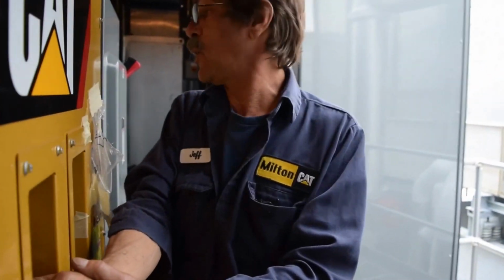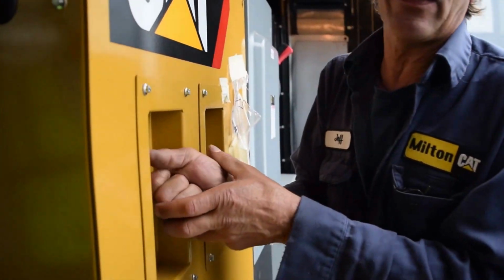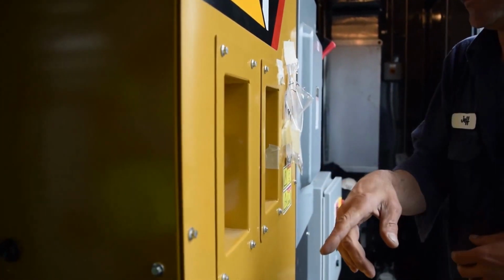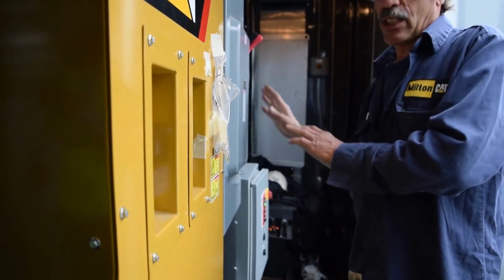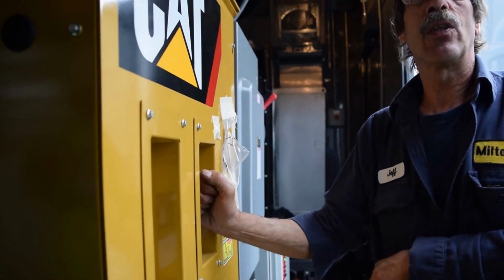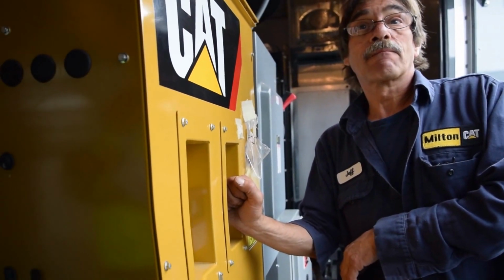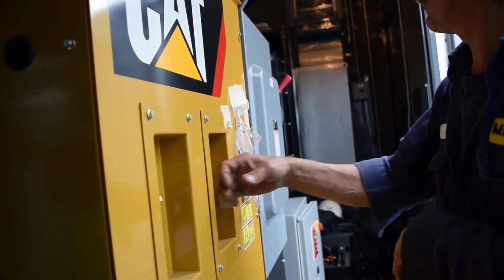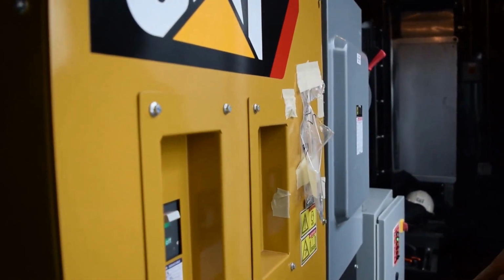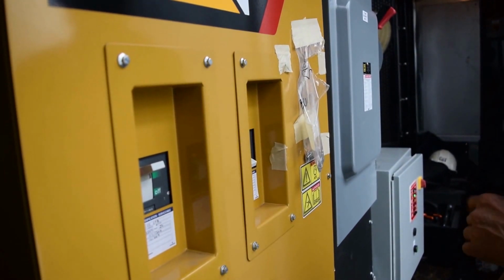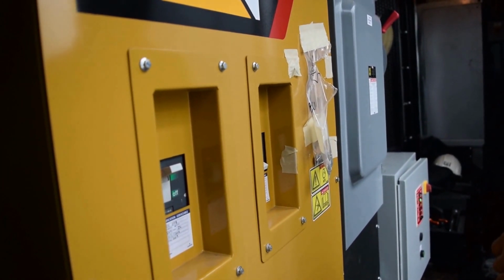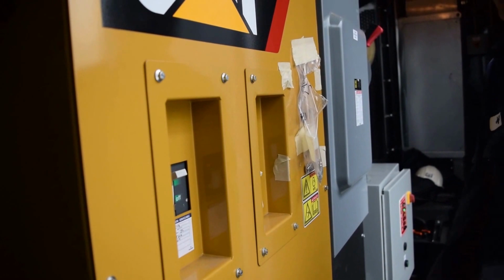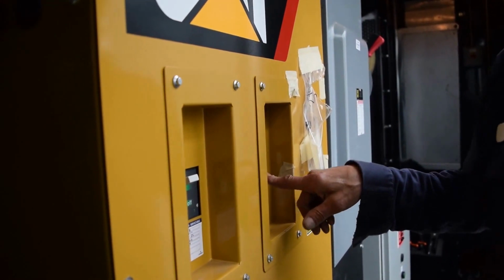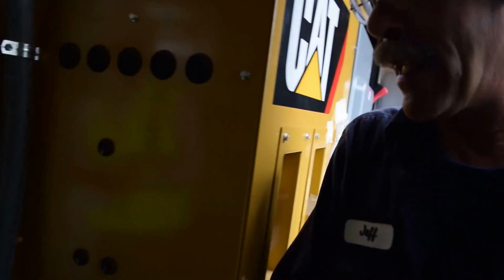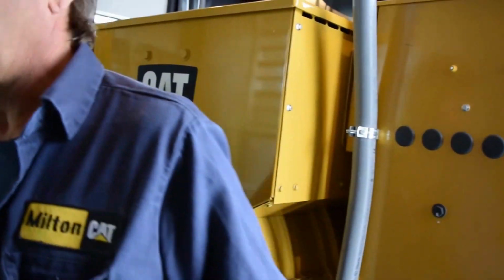And I believe this is the only breaker that is on a shunt trip on this unit. Everything else is fuses. And this is your load bank circuit breaker. We leave that off. We don't need to be running power during runs for obvious reasons. But during a monthly test or whatever, you turn that on, and just let me squeeze by, and you have your load bank controls right here.